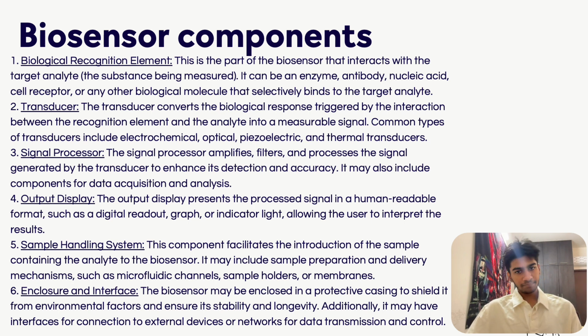Number four, we have an output display. This is the display that the user views. The output display presents the processed signal in a human readable format, such as a digital readout, graph, or even an indicator light. Number five, the sample handling system. This component facilitates the introduction of the sample containing the analyte to the biosensor. It may include sample preparation and delivery mechanisms, such as microfluidic channels, sample holders, or even membranes. Next we look at the enclosure and interface. The biosensor may be enclosed in a casing to shield it from environmental factors, and this ensures its stability and longevity. Additionally, it may have interfaces for connections to external devices for data transmission and so on.